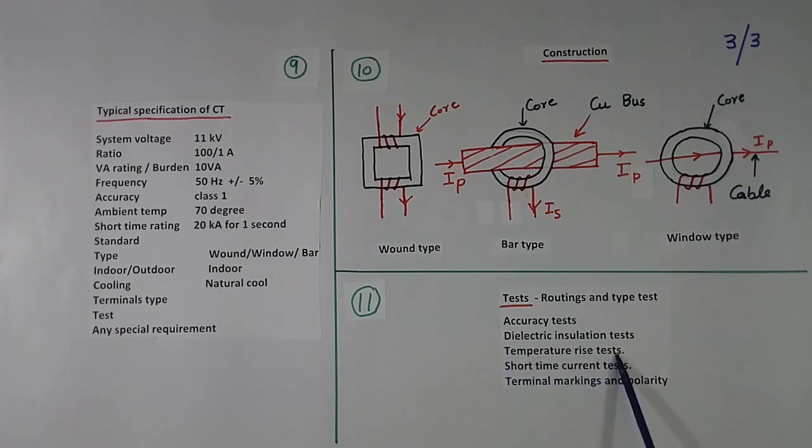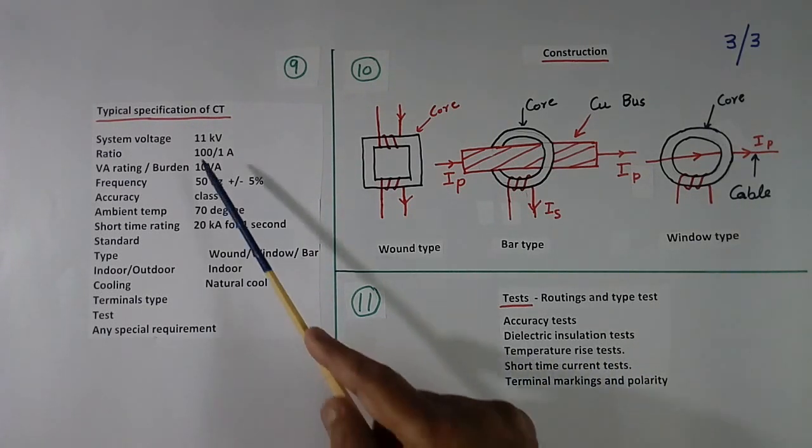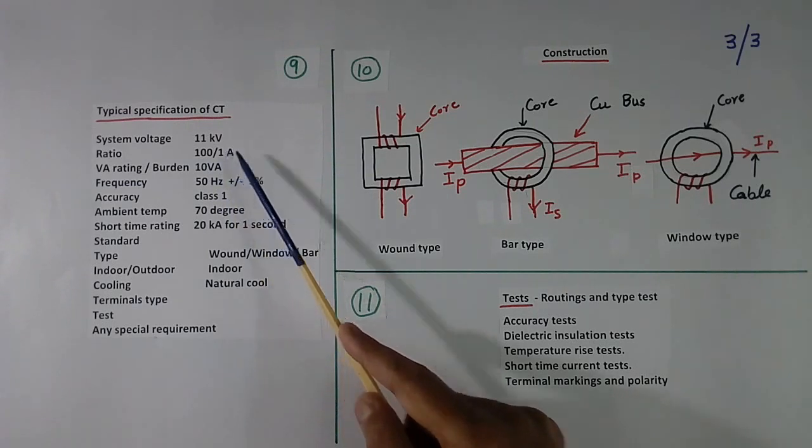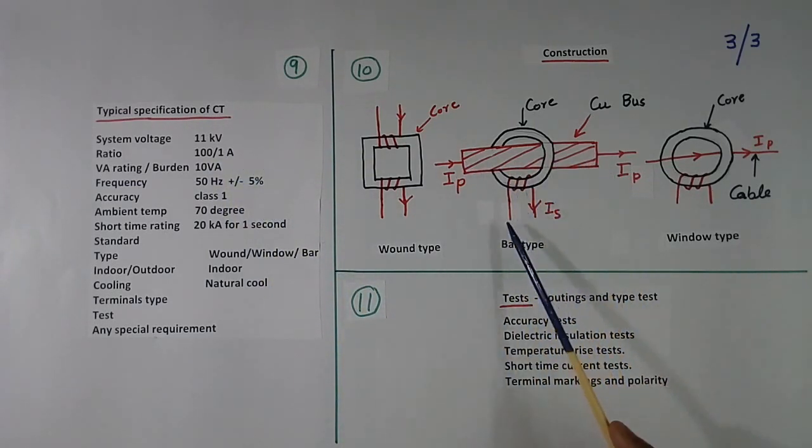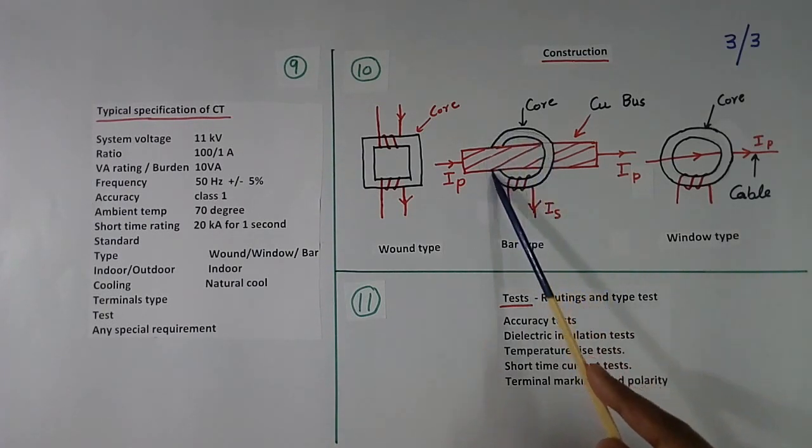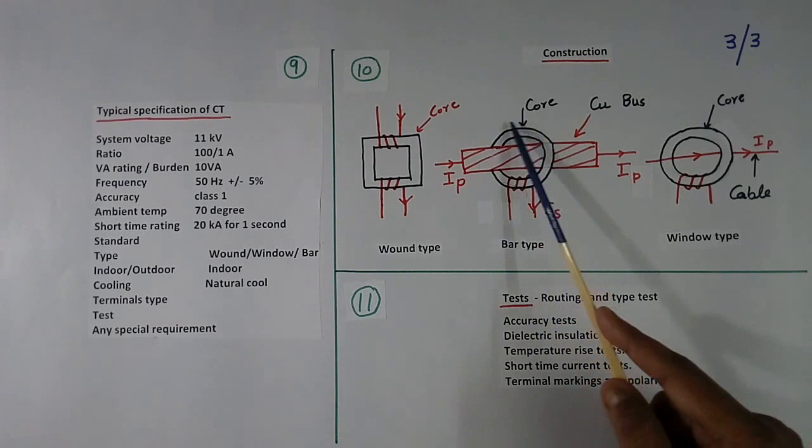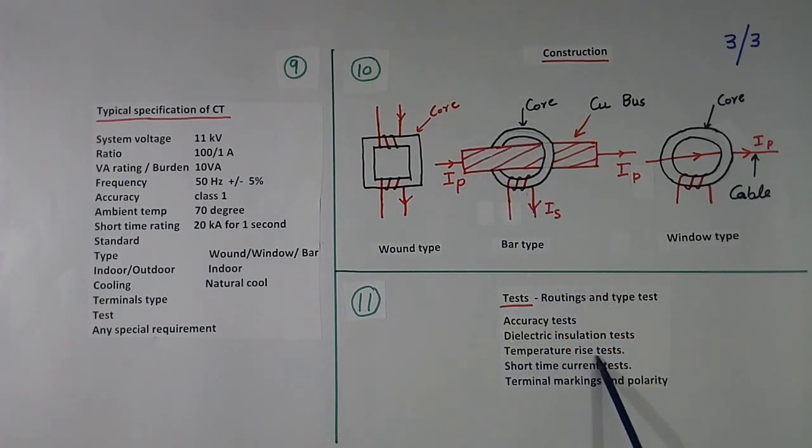Then temperature rise test. If it is 100 by 1 ampere, we will give full 100 ampere here and full load here. And check whether it is becoming hot or not. Or how much temperature is rising. That is called temperature rise test.